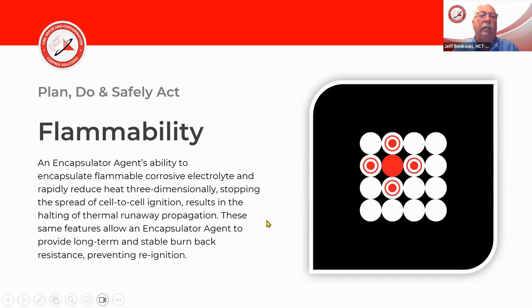When we look at these types of fires, and all the testing done with foams, powders, gels, and inerting gases - those are all very ineffective because they do very little to remove the heat. Whereas with the encapsulator agent, we saw how we can take temperatures in excess of 1,300 degrees down to 100 degrees in seconds.